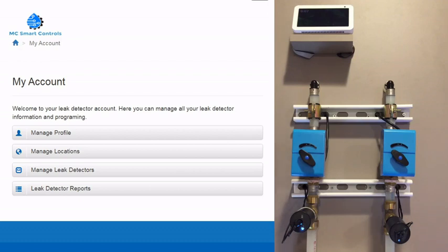First being flow detection to monitor both the hot and cold water services in the home. Number 2, point of location sensors monitor water on the floor in the immediate area, for example under appliances. Number 3, automatic ball valve shutoff of the water services in the condo. Number 4, building device cloud server for building managers and concierge oversight. And finally, number 5, integrations to Amazon Alexa, Google Assistant, Crestron Control 4 and Savant using IFTTT triggers so the homeowner can be notified and easily control the system in the case of a leak in the home.